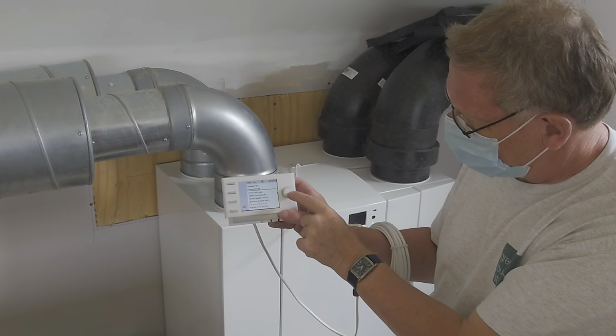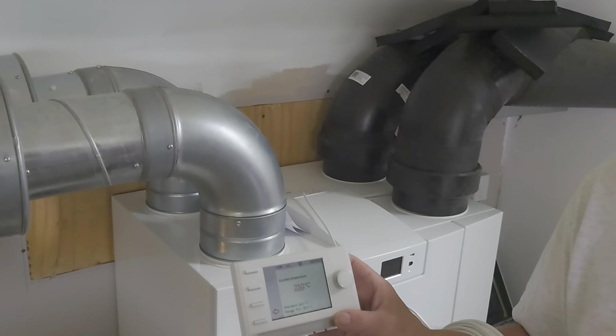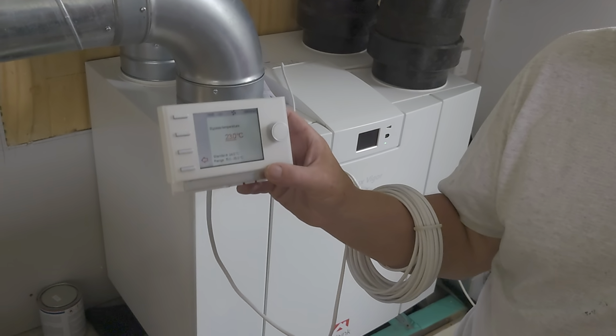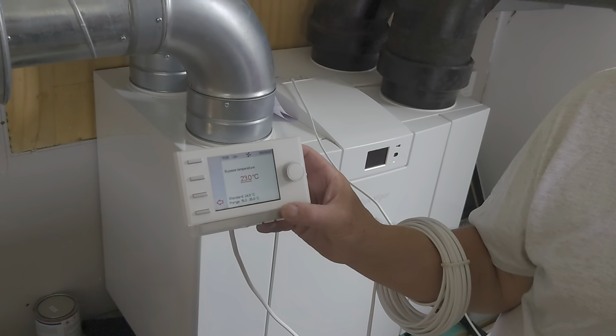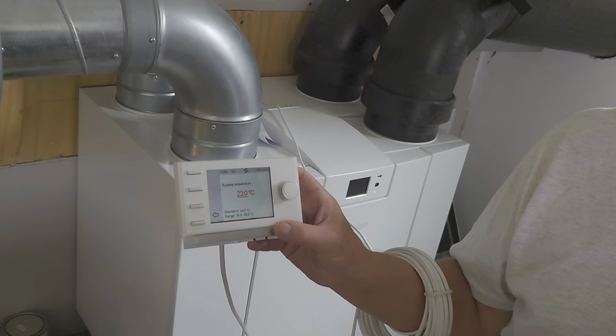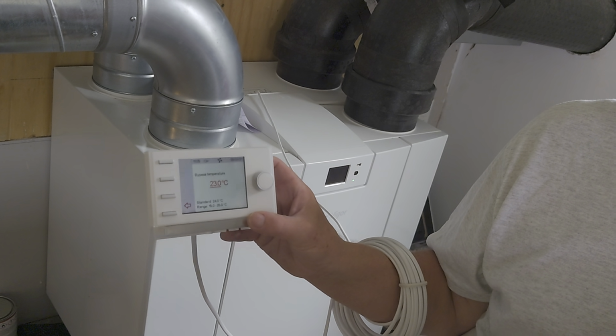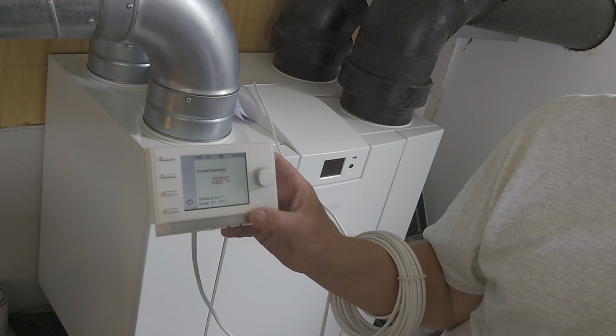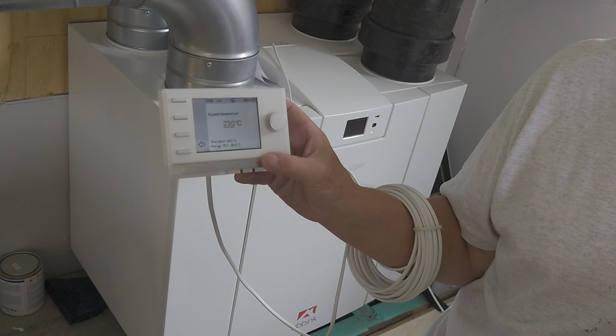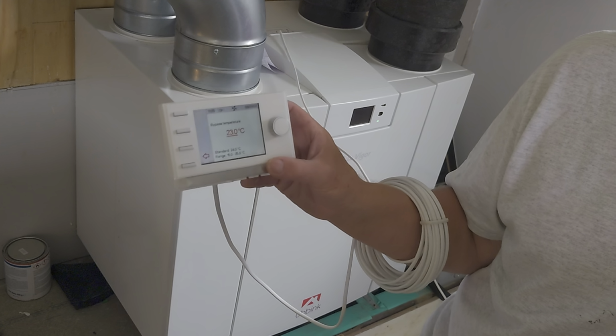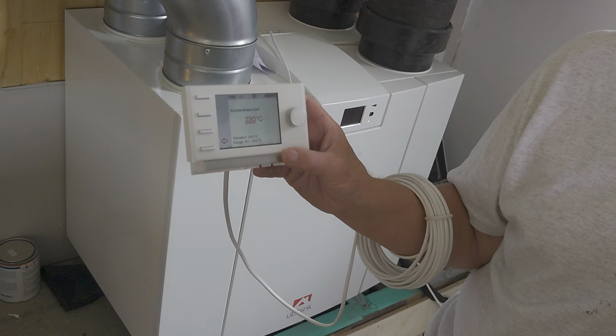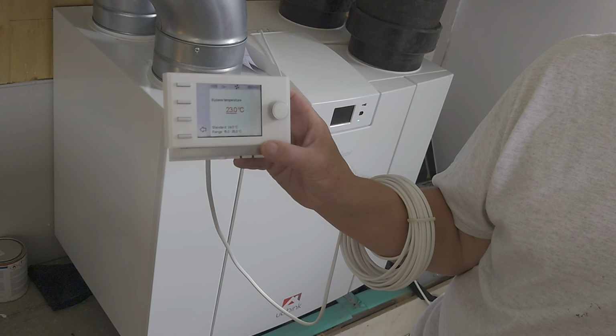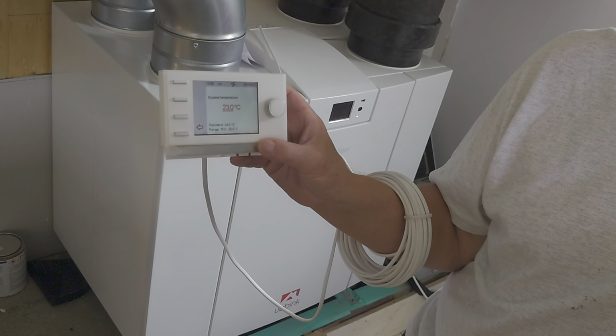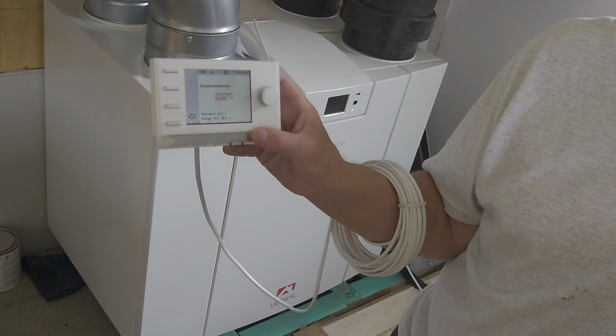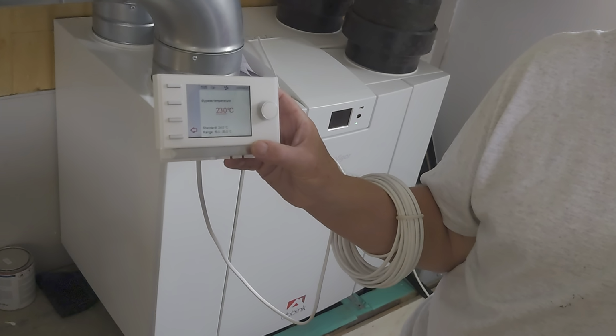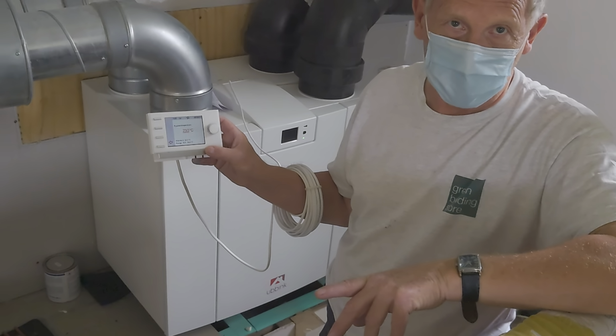Bypass temperature, so I set it to 23 degrees. You may want to alter that. What that means is if the average internal house temperature starts to creep above 23 and it is cooler outside, it'll go into bypass mode. You might be thinking 23 is a bit high, and you can put it a little lower if you wanted to, but I wouldn't recommend much lower than that in winter, because we don't want your heating system trying to heat the house up and the ventilation system thinking we're getting too warm now, I'm going to start dumping the heat. So you don't want the two systems fighting each other.